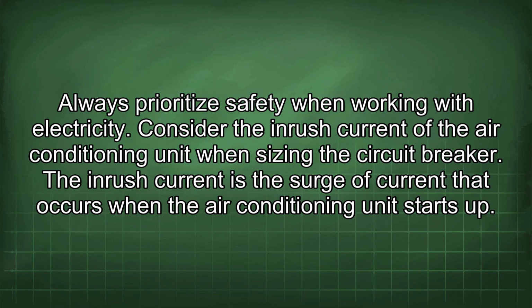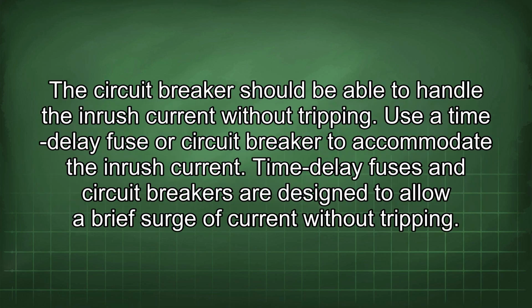Consider the inrush current of the air conditioning unit when sizing the circuit breaker. The inrush current is the surge of current that occurs when the air conditioning unit starts up. The circuit breaker should be able to handle the inrush current without tripping.